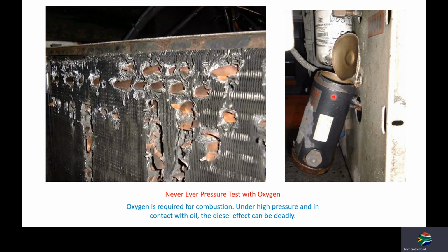And here you can see an accumulator that also exploded. So you also never ever test with oxygen. And also, just as a note, when you put your oxyacetylene regulators on, you never ever put oil on the thread of the regulators. If it's battling to turn into the bottle, you never ever put oil, because the same thing can happen. As you open the pressure to the oxygen, you could have a catastrophic explosion and a fatal injury as the oxygen combusts with the oil under high pressure.